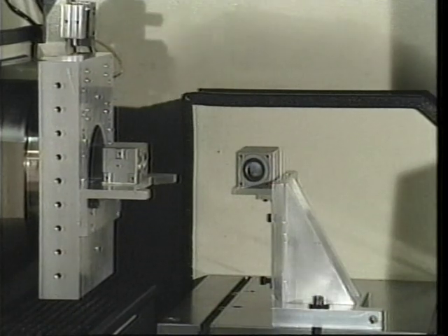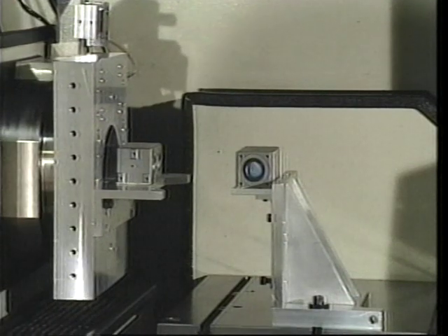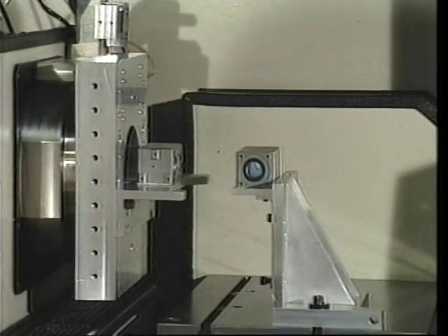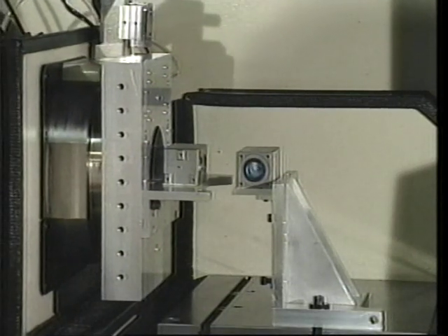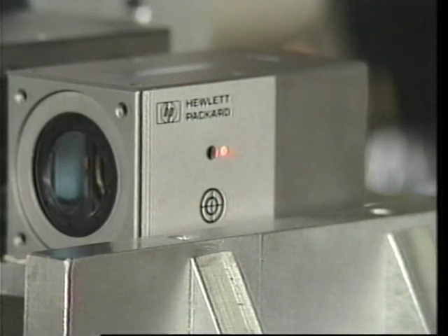The z-axis slide is moved so that the reflector and interferometer are at their minimum distance of separation. That is, the z-axis slide is jogged to the z=0 position. With the z-axis slide at 0, the position of the laser beam is adjusted until it passes through the 3 mm hole in the target.